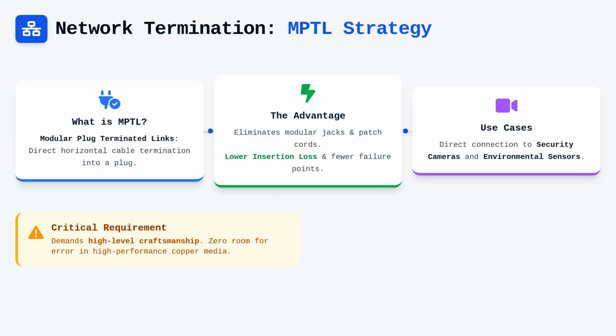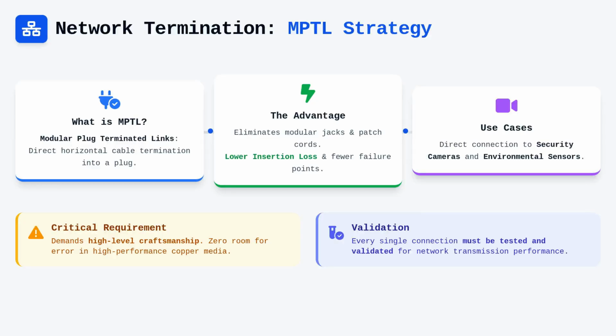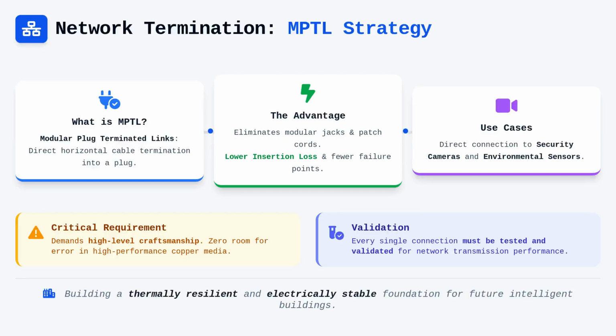However, this demands a high level of craftsmanship during installation because there is zero room for error when field terminating high-performance copper media. Every connection must be tested and validated to ensure it meets the transmission performance requirements expected of the broader network. As we architect these infinitely scalable systems, we are not just installing wire, we are creating a thermally resilient and electrically stable foundation for the intelligent buildings of the future.